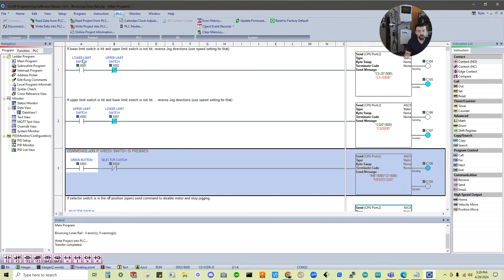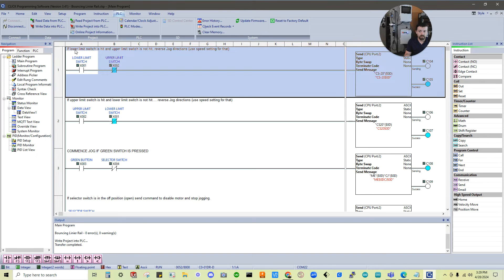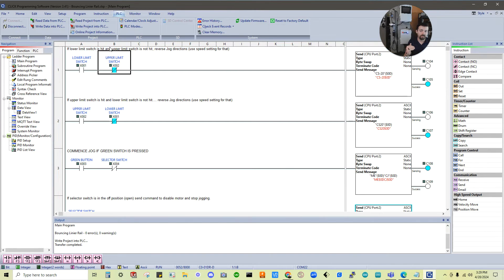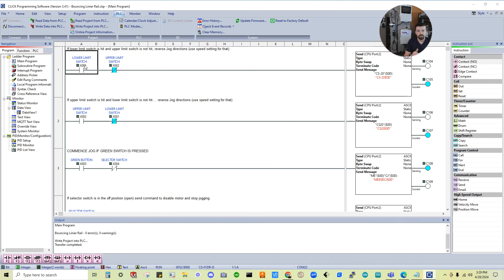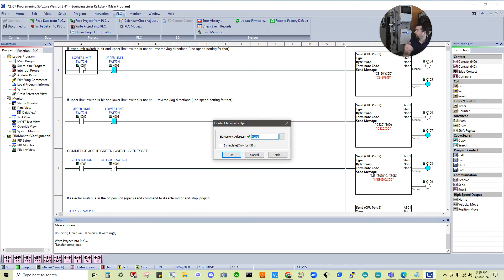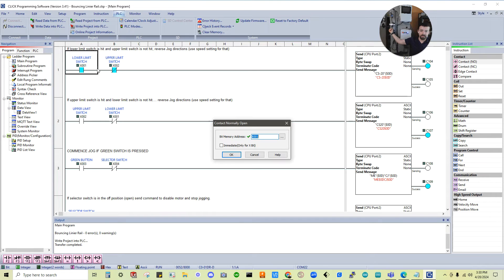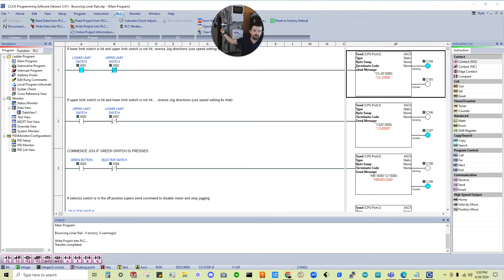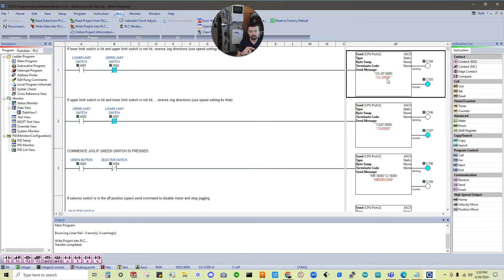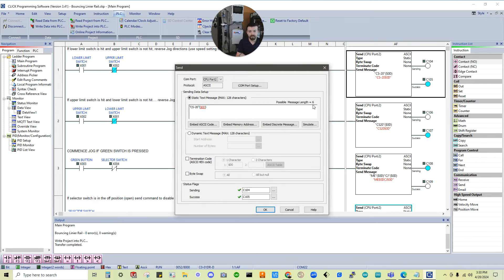These are just called rungs. I put rung comment on each. So you can see like this rung one has a comment. If lower limit switch is hit and upper limit switch is not hit, we're going to reverse jog directions. And then we're going to use a speed setting for that. So if this lower limit switch gets hit, you can see upper limit switch is not hit. It's gotten through these two commands. Everything on the rung is highlighted.